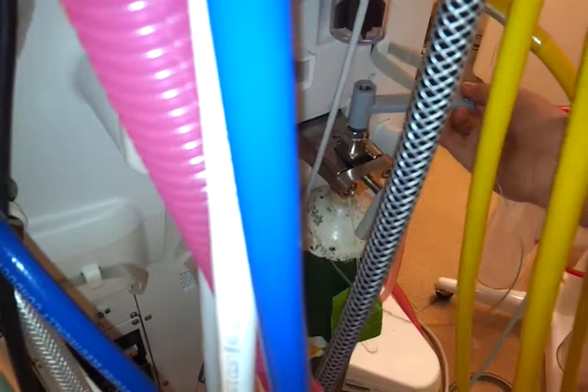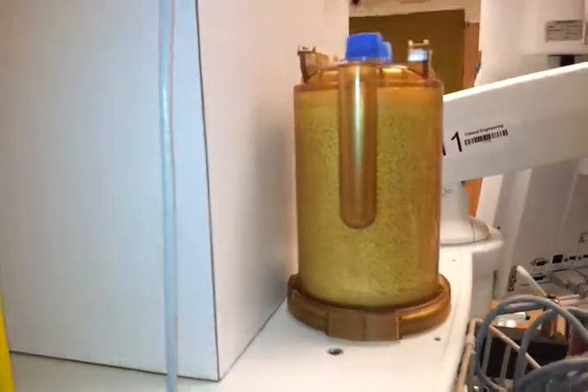You want to open the oxygen cylinder to see what the pressures are, which will show you. It comes up on the gas machine after. Usually turn it about 3 times. So open it 3 times, and I'm just going to close it again. 2, 3. I usually check the CO2 canisters, so they always have the extra one up here. And the one in use is always right here, and there's the collects water down here, so if there is water you can empty it, but there's nothing right now.